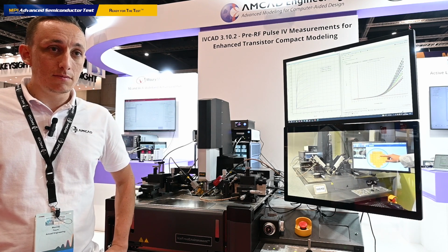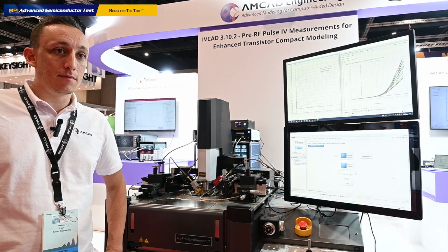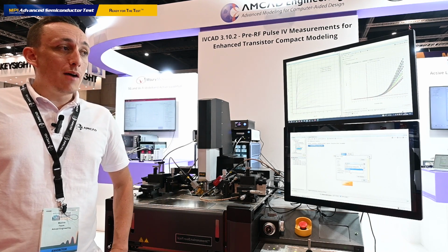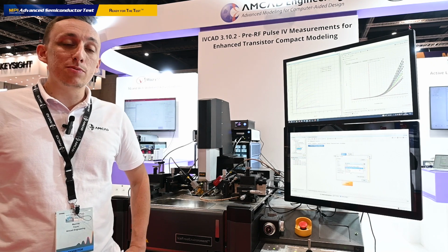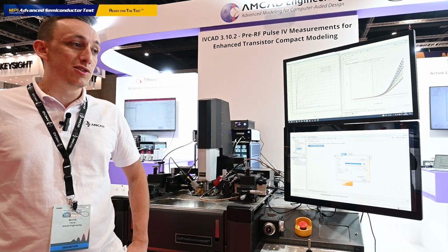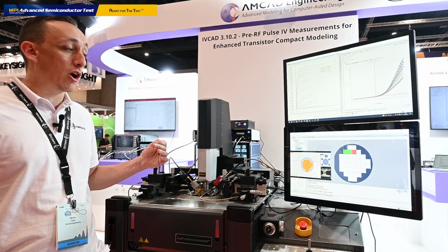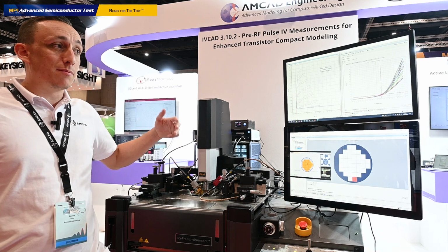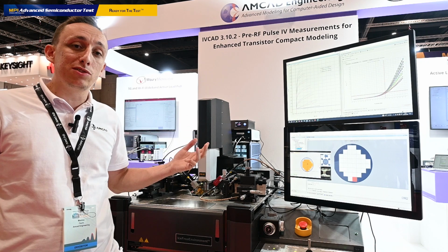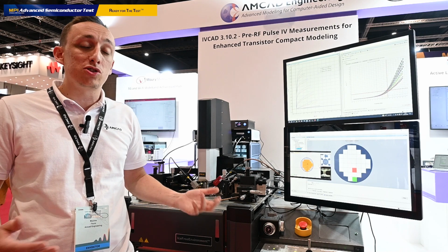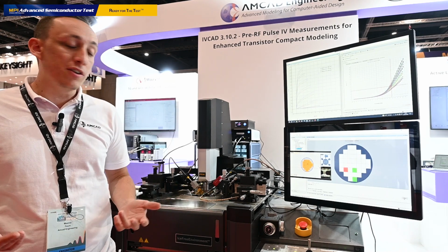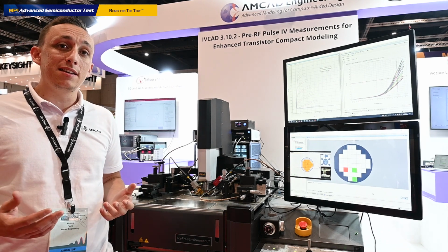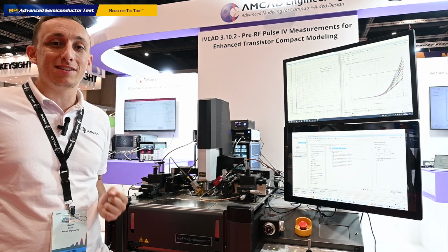What kind of feedback have you received from engineers or researchers who have used this new method? As this method is quite new, our customers say that this measurement technique is very interesting because it uses exactly the same instruments that they already have in the lab, because we use a VNA and a pulse IV system, which are instruments that are necessary to use when you extract the measurement to do a compact model. Moreover, this measurement technique permits to highlight very quickly the trapping effects on the device measured.